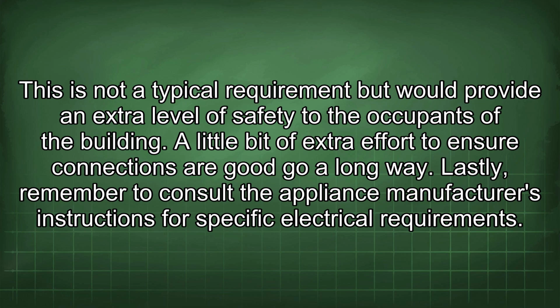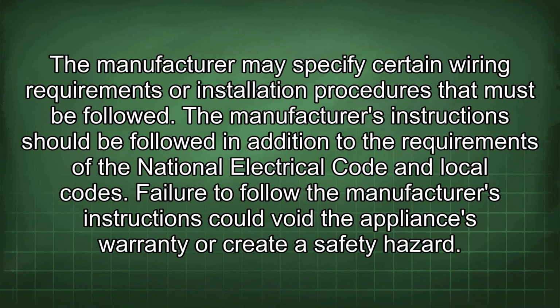Lastly, remember to consult the appliance manufacturer's instructions for specific electrical requirements. The manufacturer may specify certain wiring requirements or installation procedures that must be followed. The manufacturer's instructions should be followed in addition to the requirements of the National Electrical Code and local codes. Failure to follow the manufacturer's instructions could void the appliance's warranty or create a safety hazard.